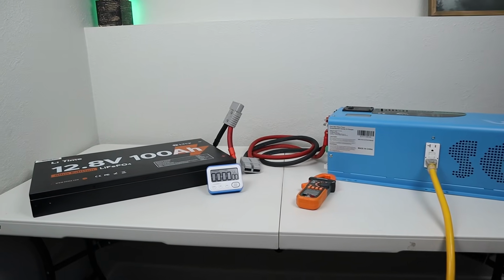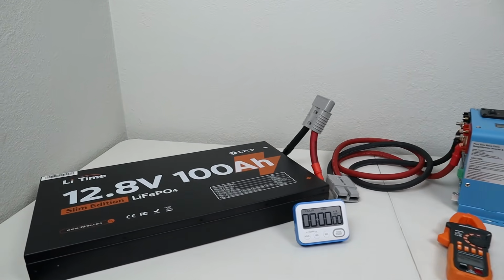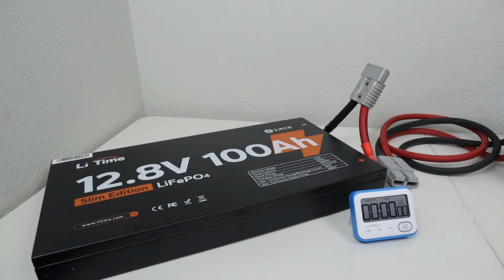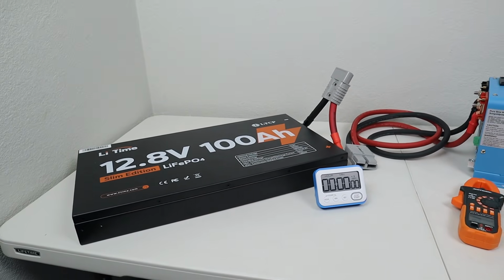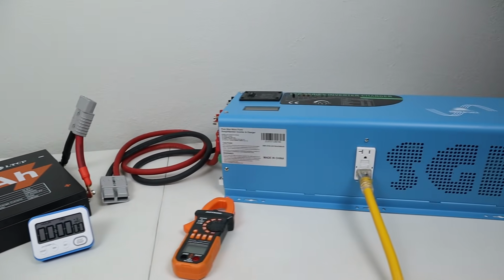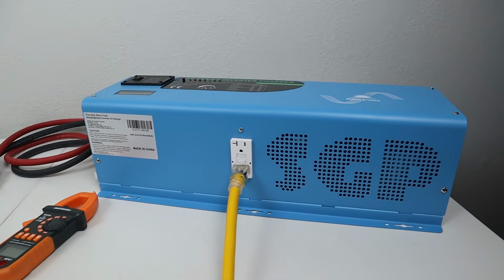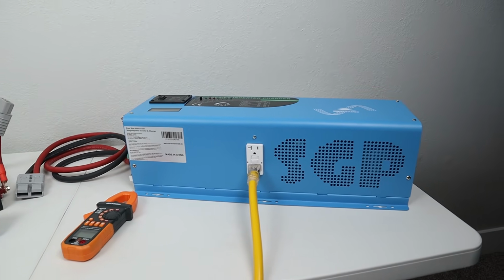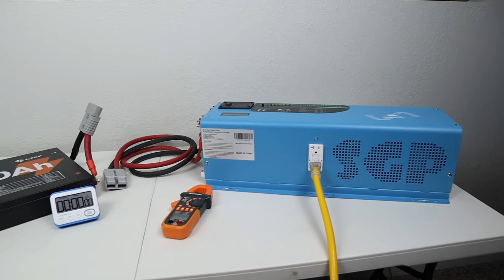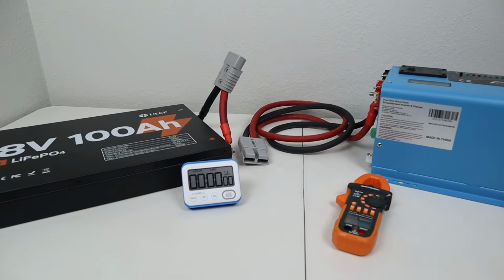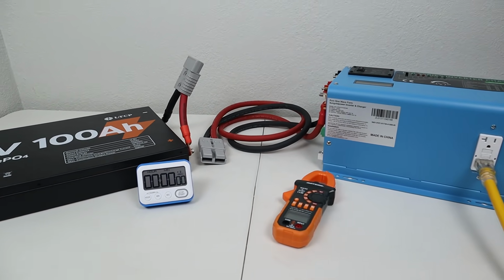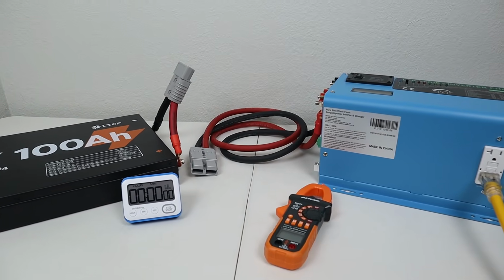Moving on to the next test, I've charged up the battery and now I want to know if it can handle 100 amps continuous for 15 minutes without shutting down. So we're going to connect it up to my SunGold Power 4000 watt low frequency inverter with a load of about 1280 watts, or 100 amps. We'll be timing it with this stopwatch, and of course we'll be checking in with my clamp meter to make sure we stay at 100 amps throughout the entire test.